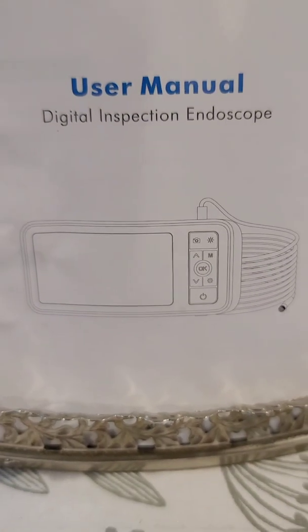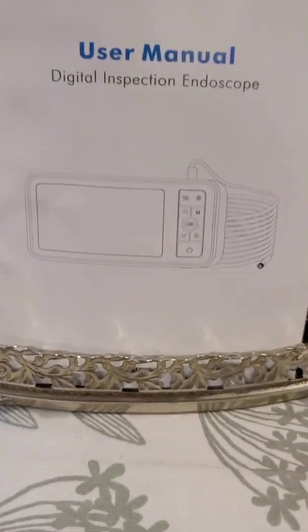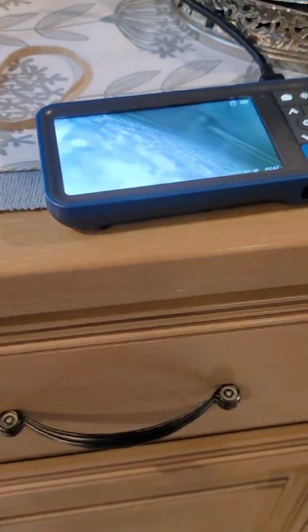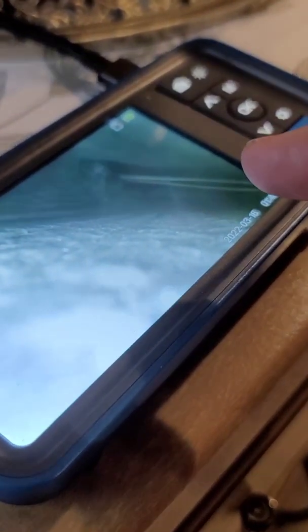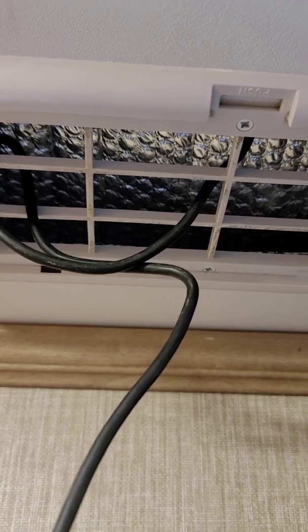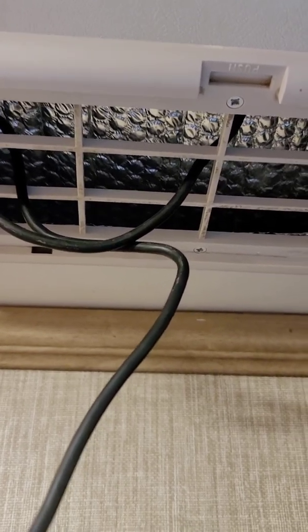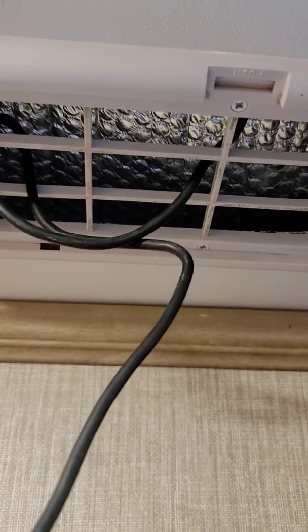Here's the ticket right here: a digital endoscope. It has a display screen with a 16-foot cable. As you can see, I do have electrical up in there, but it looks clear. I'm only going to be cutting in about 1/8 of an inch, so I'll be fine. The other end of that cable is run into the ductwork so I can see what's going on.